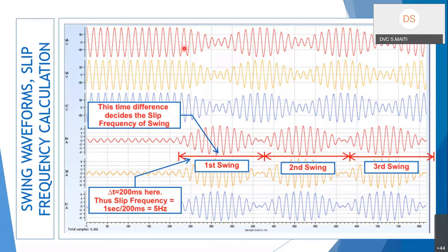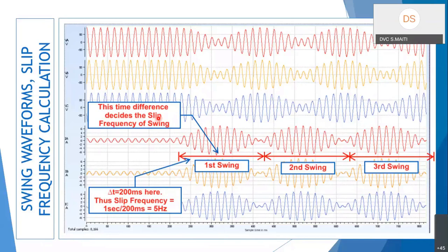This picture of a generated power swing from a test kit is important. The slip frequency is the cyclic envelope frequency of the variation — not the 50 Hz power system frequency. From the diagram, the time between envelope peaks is 200 ms, so the slip frequency is 1 second divided by 200 ms, equal to 5 Hz. The time difference of the envelope maximum and minima gives the slip frequency.